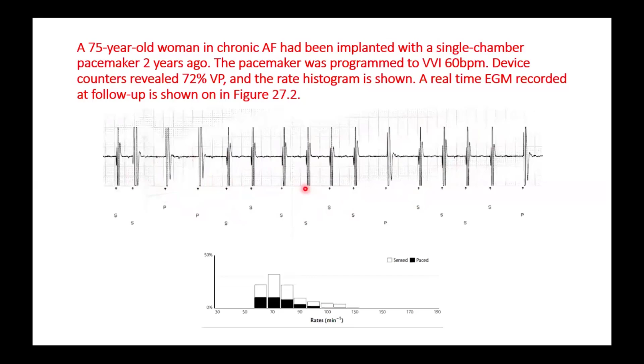And this is the differential diagnosis of pacing at a higher rate than the programmed rate. You should always think of all of these. First, the rate smoothing and rate regularizing algorithm, and this feature is programmable actually. Second, the rate drop response, which is programmed in Medtronic devices for cardio-inhibitory syncope. When a sudden drop in heart rate of a certain amount occurs, it paces at a higher rate for an intervention duration, usually pacing in DDD mode at a rate of 100 for 2 minutes.